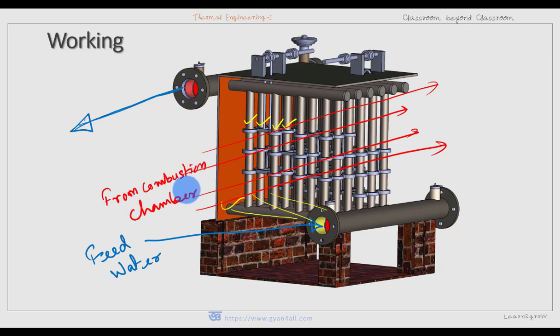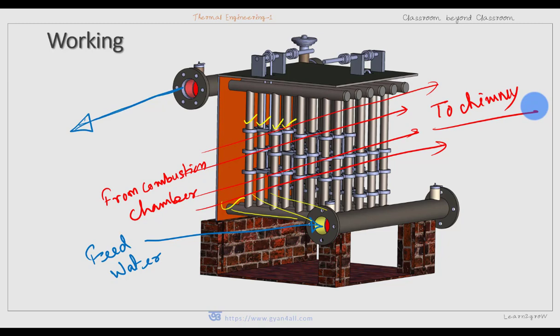Hot gases from the combustion chamber move to the chimney, and during this time heat transfer takes place. Because of that, while the water is moving from the bottom header to the top header, the water is heated to some extent. This hot or warm water is then used as feed water for the boiler. While the economizer is in operation, the scrapers on the tubes are moved up and down continuously with the help of the chain and gear arrangement so that soot deposited on the pipes may be removed.